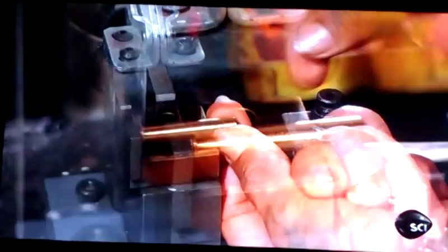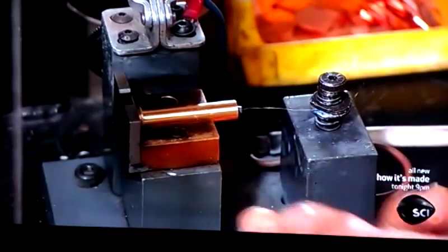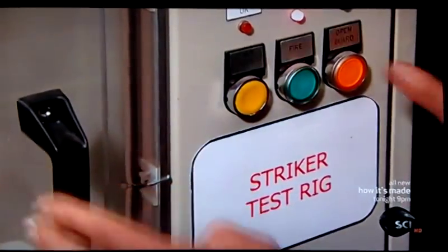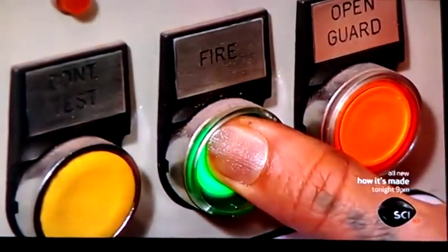This test run shows how it all happens. The pin's ignition wire is wrapped around an electrical post. Workers clamp down the pin and position the pendulum that swings to indicate the amount of force with which the pin fires. A jolt of power detonates the explosive, causing the pin to protrude — signifying a blown fuse.